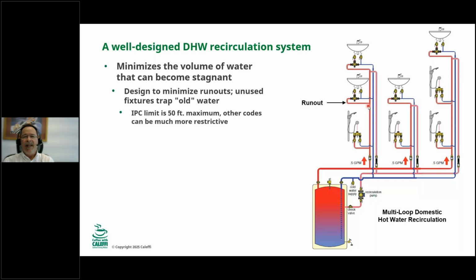We want to minimize that, and some codes actually specify 50 feet, for example. The IPC specifies 50 feet. I know that local codes are more stringent. So if you can type in the chat, or if you have a question, tell me what this length is in the jurisdiction where you live. We'd be interested to find out. So as a designer, you want to minimize those. Why? Because anytime that fixture is not used, you've trapped old water. The water is trapped in that runout, and it can get old and potentially contain bacteria.